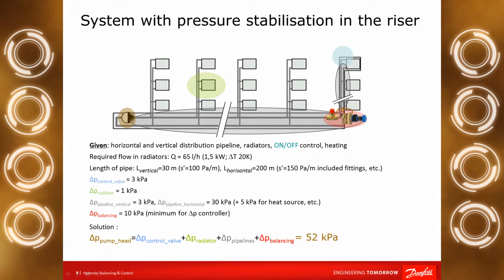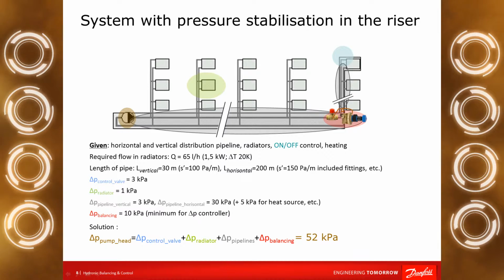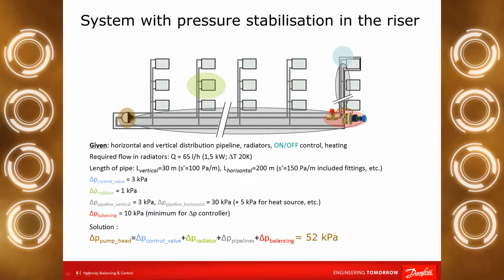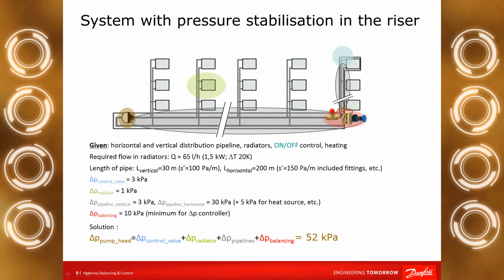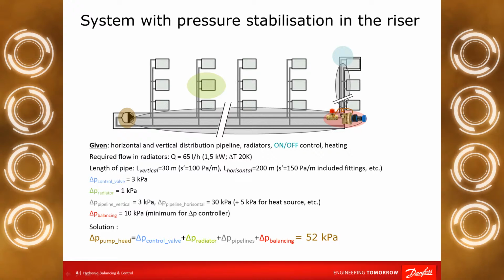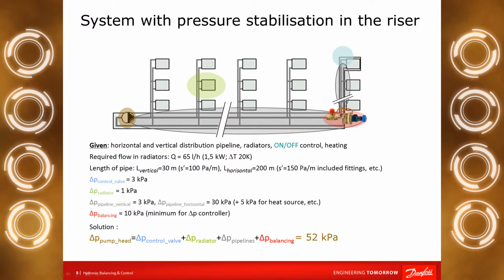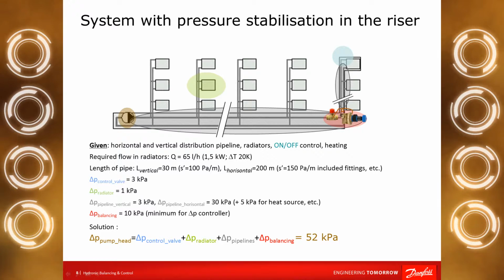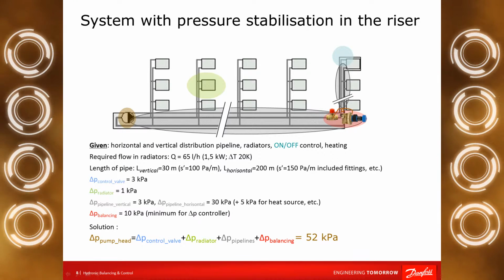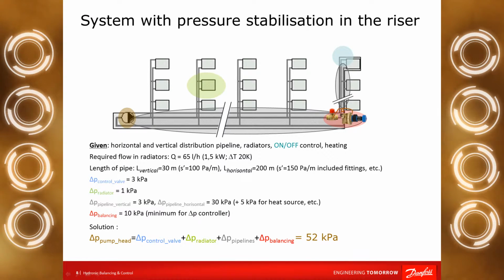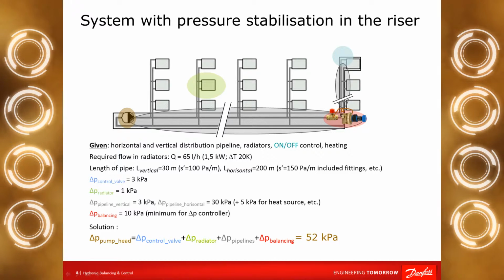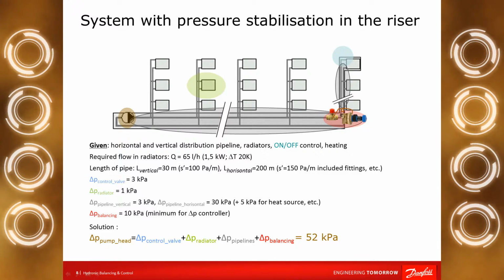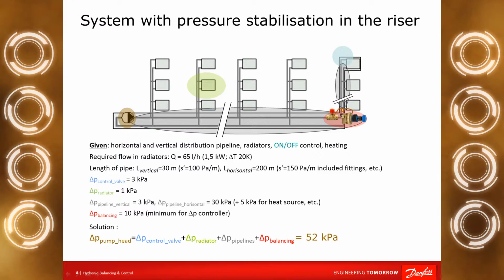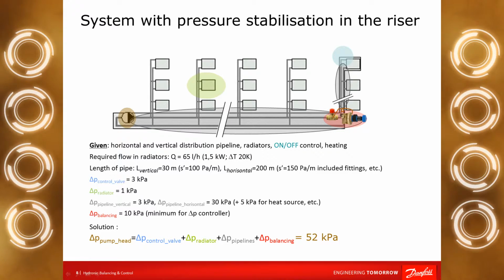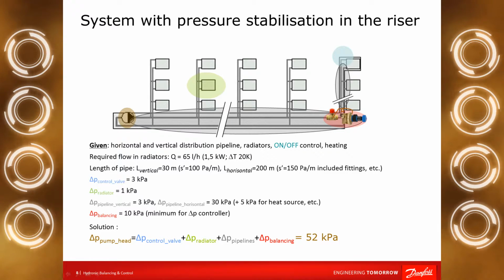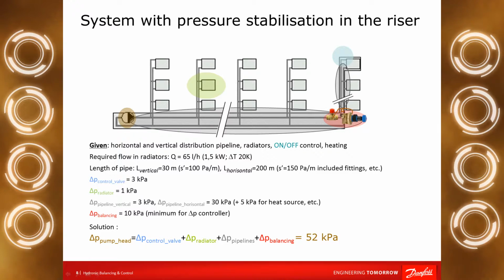In this case, we presume the same system, exactly the same system, lengths and equipment, except this different delta P controller in the bottom of the riser. We can calculate the pump head. You can see here a little bit bigger pump head we need, just because we have this delta P controller, and for proper operation of this delta P controller, we need minimum 10 kilopascal pressure drop on it, and with this we can ensure right constant delta P control for the riser.